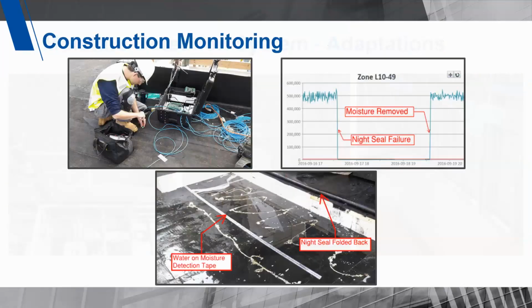Now, one of the major advancements of the moisture detection system was the ability to start pulling that data in construction. These systems need power and data. Usually the sensors would go down, but power and data wouldn't be in the building for 6 months to a year. The system would get plugged in and the vapor barrier would read wet. Every single project, everywhere in the entire world. Nobody could tell when or where the moisture intrusion began, but what could be confirmed is that there's always standing water on the vapor barrier.